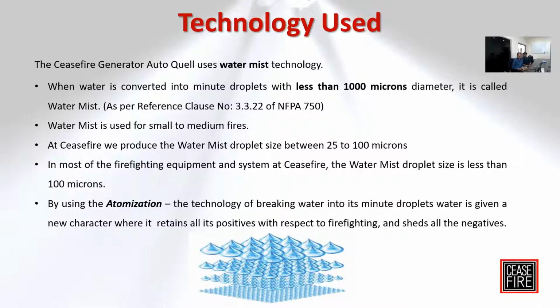See, water converted to less than 1000 microns is called water mist, that's as per NFPA, but we produce water mist which is between 25 to 100 microns, and as we talk about this single fluid system, it is always less than 100 microns. Normally, when the pressure is at the peak, it produces almost 50 to 60 micron size. But at the peak max, it will be 100 microns. It works as an atomization technology where the pressurized water goes inside the nozzle and is broken into fine particles, and therefore a small particle size between 60 to 100 microns is created.